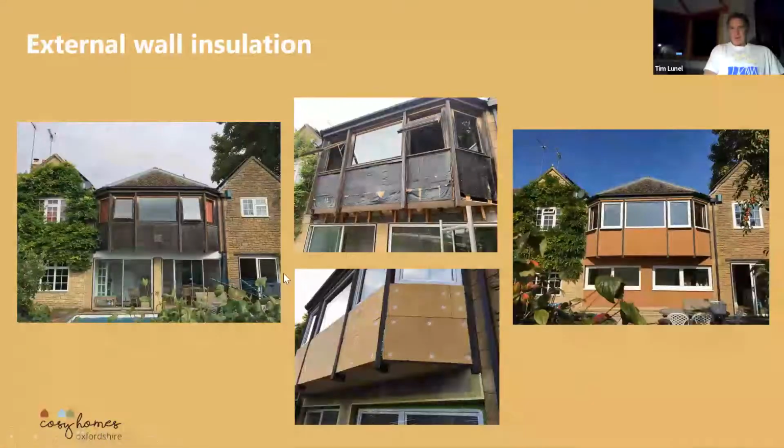The wood cladding got taken off right back down, and wood fibre is the basis there, with some fall underneath to make sure we had the depth as well, but we extensively changed the insulation here. And then here, these windows were taken out, and what you can see on this side is we've now got thick, I was trying to remember what the thickness is, I think it's 200 mil, it might be more than that, thick walls now with combinations of insulation on the outside and breeze blocks and things to make sure the U values are right down for these walls.